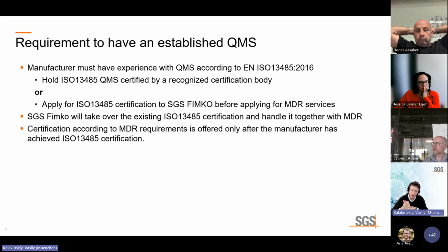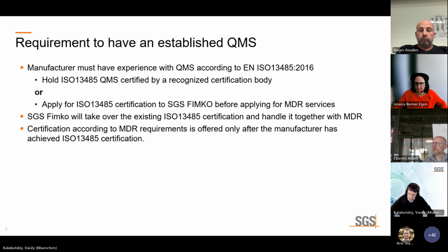So to make sure that the customers that proceed with MDR conformity assessment procedures are mature enough, we have this requirement. The company must hold ISO 13485 or apply for it to SGS FIMKO before going for MDR services.